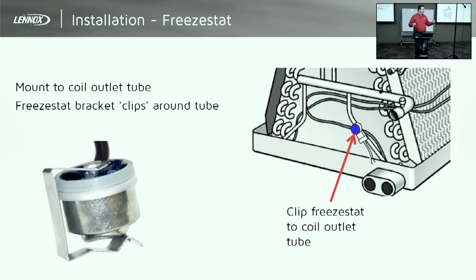So if that's happening on your system and you're running at maximum capacity with all your zones open, one, I check and make sure your airflow is correct. And with all your zones open, that shouldn't be that big of an issue. But if it is happening due to low ambient, then really all you can do at that point is block the coil off. I had to do that a few times in a couple of site visits recently, where in the morning it's 60 degrees outside, sometimes 55 degrees outside, a nice hefty trash bag. I'll block it off until you get that liquid pressure up to 350 maybe. 325, 350 I think is normally where most of our charging charts will say you should be on a 95-degree day.